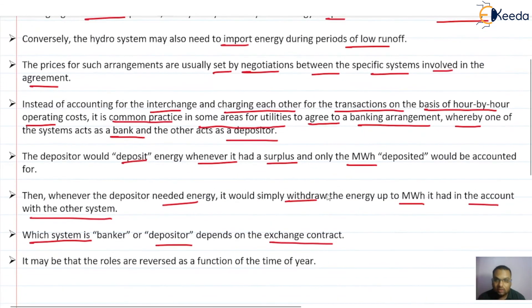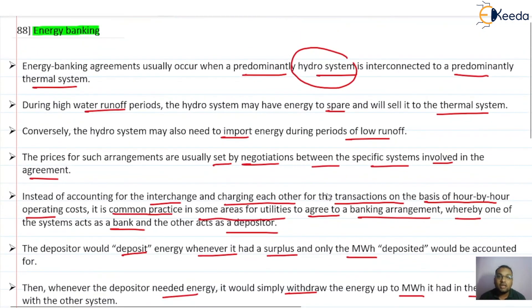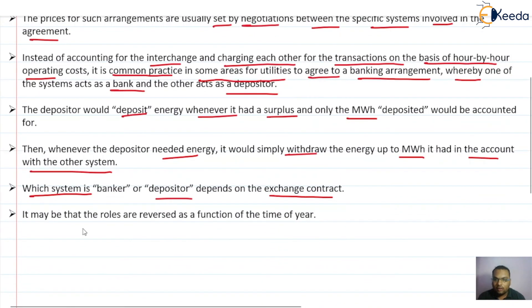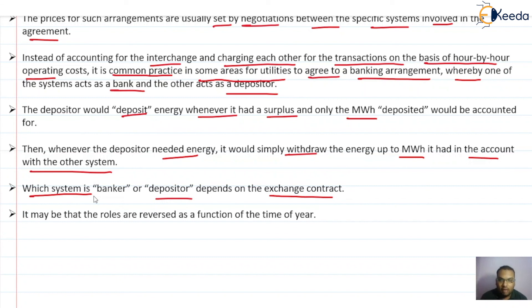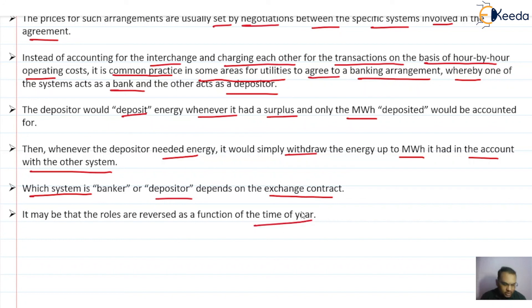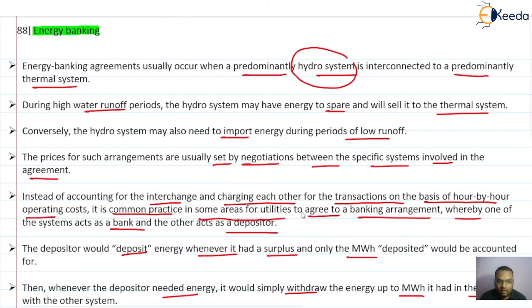This is why this type of interchange is called energy banking. The role of who acts as the bank or depositor depends on the contract and how the systems agreed to have the interconnection. This role of either bank or depositor can be reversed as a function of time of year. This is how energy banking interconnections are done between utilities.